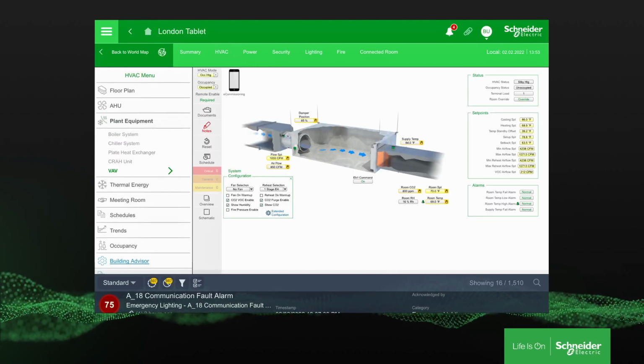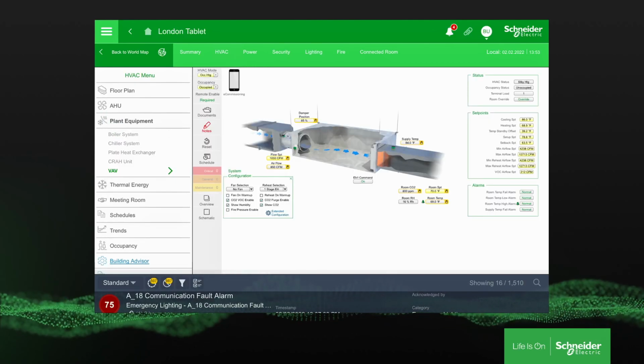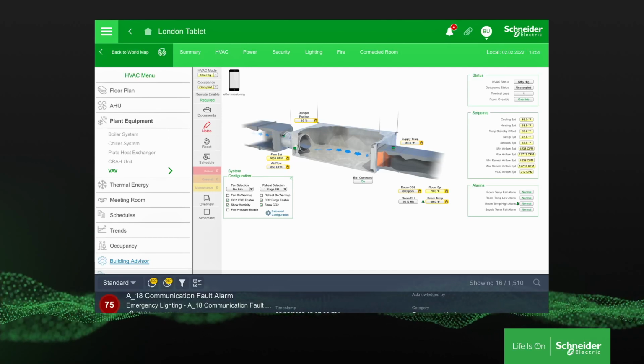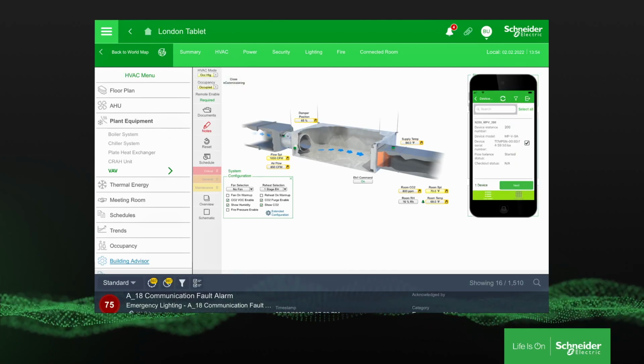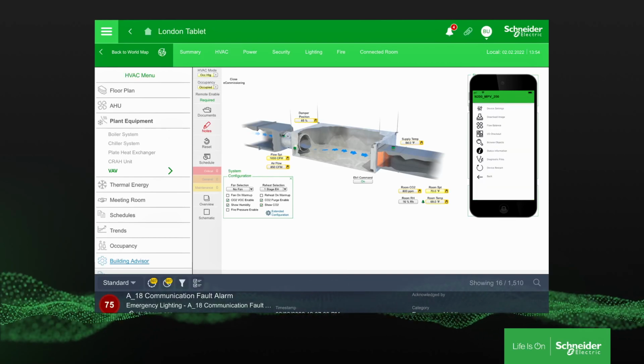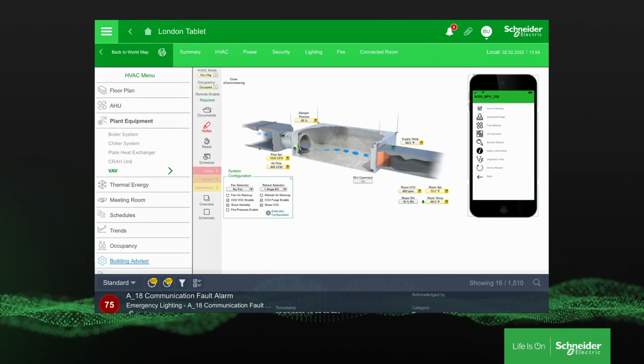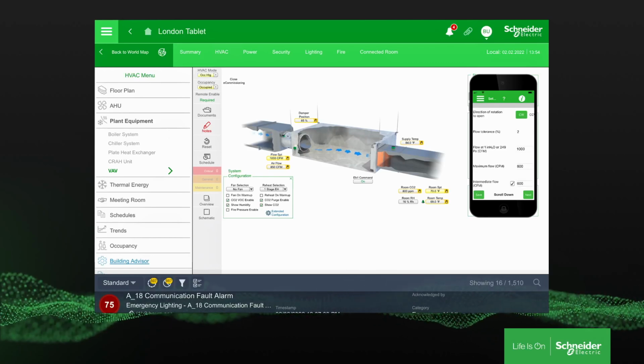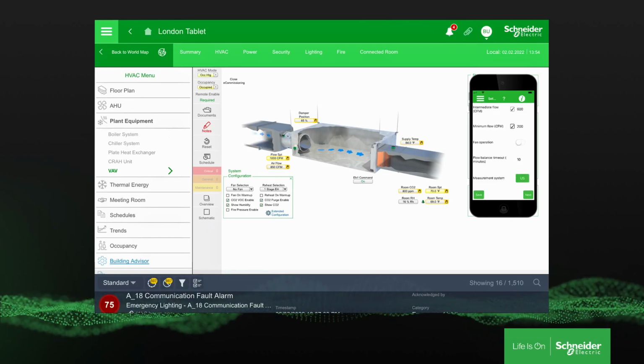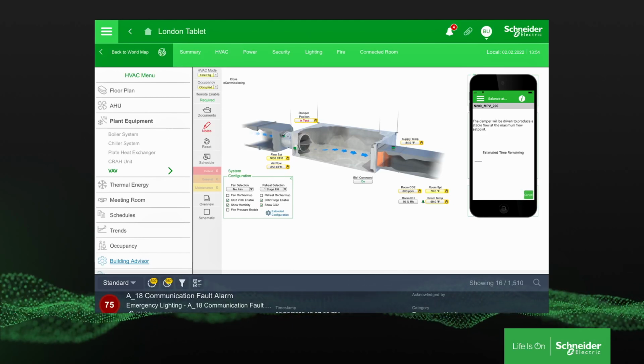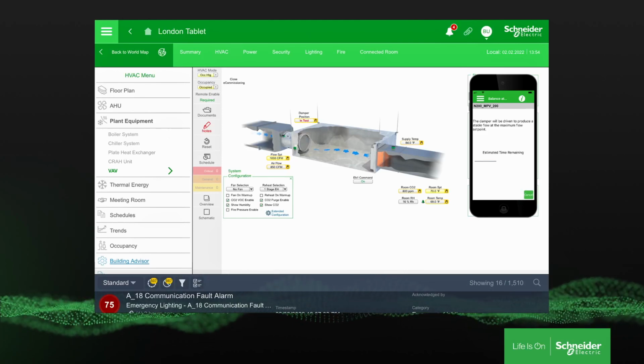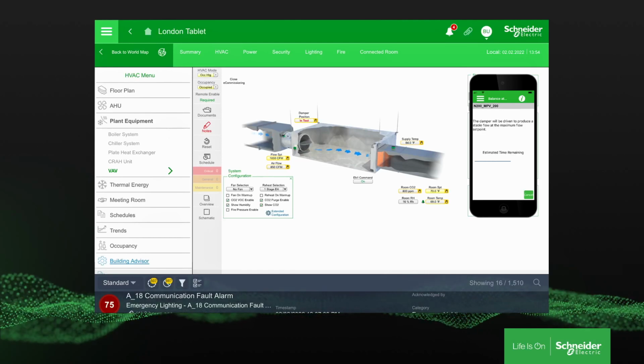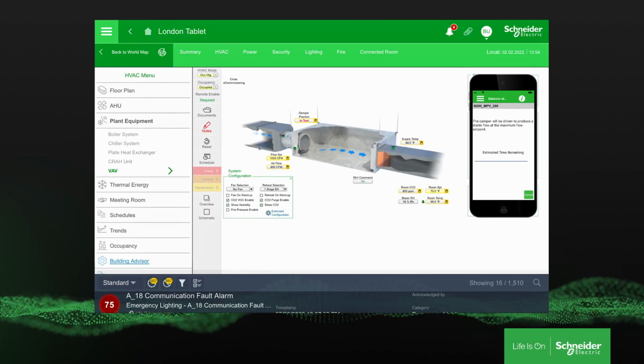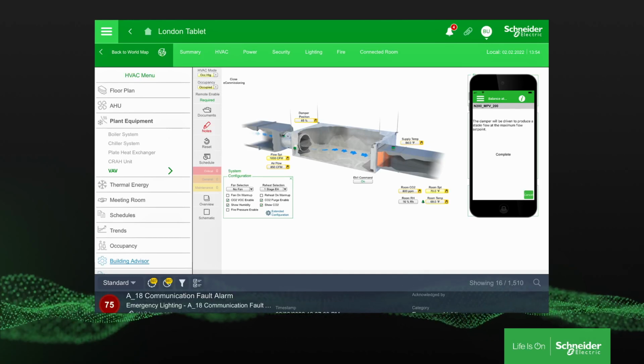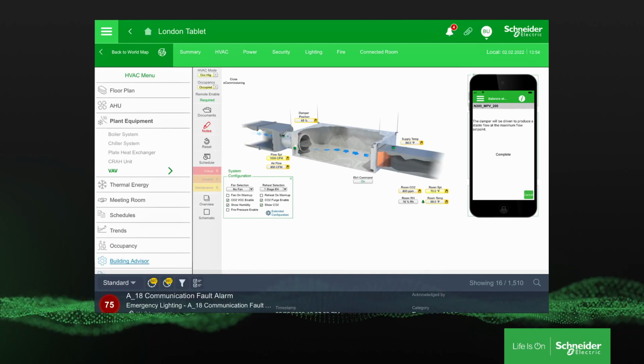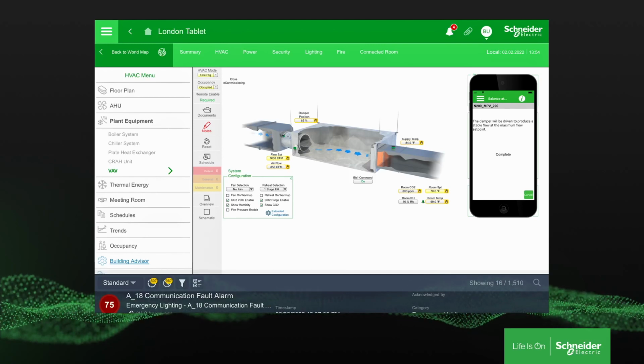One of those chores was to follow up on another complaint about inadequate air delivery in the boss's office. I installed the e-commissioning app on my phone last week, so I should be able to rebalance that box right now and get a report that I can send over to the boss. Yep, that looks like the right VAV box. Let me navigate to the balance testing. First, I can confirm that the current settings are correct. Then I can start the test and watch the damper get opened and closed and the readings tracked and recorded. When the test is complete, I get a mini report to verify.